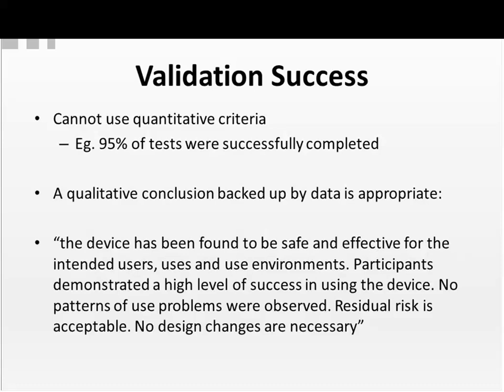And the qualitative conclusion would be: device has been found to be safe and effective for the intended users, uses, and use environments. Participants demonstrated a high level of success in using the device. Notice we use the term high level, not 100% or 80%, high level. No patterns of use problems were observed. Again, we're using the term patterns. Residual risk is acceptable. No design changes are necessary.